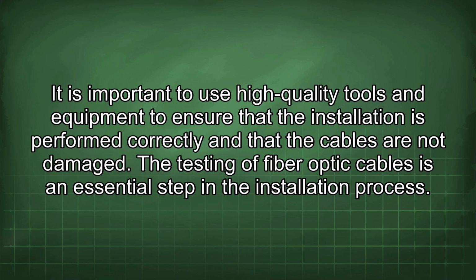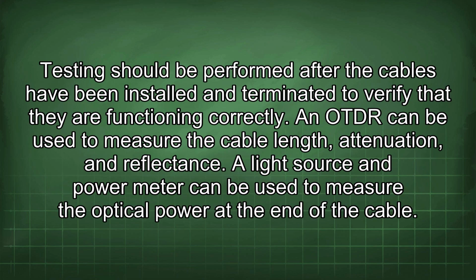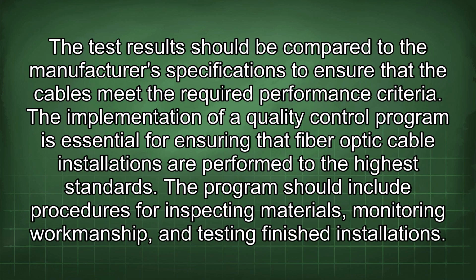The testing of fiber optic cables is an essential step in the installation process. Testing should be performed after the cables have been installed and terminated to verify that they are functioning correctly. An OTDR can be used to measure the cable length, attenuation, and reflectance. A light source and power meter can be used to measure the optical power at the end of the cable. The test results should be compared to the manufacturer's specifications to ensure that the cables meet the required performance criteria.